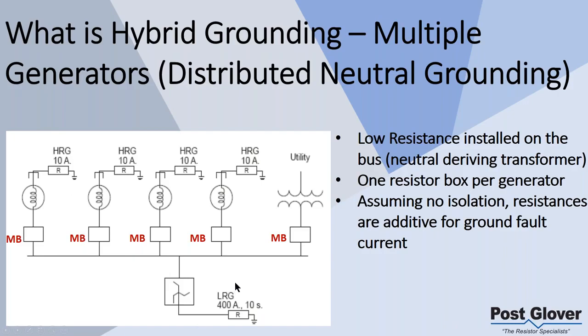But you essentially have the low resistance ground resistor hanging off of your bus right here, off of 3 wires. You're going to be deriving the neutral with what here is a zigzag transformer. So you have a neutral here. You have your resistance grounding off the low resistance ground right here. Per generator, you have a high resistance ground, typically a resistor-only package. And what happens here is you essentially trip off your main breaker if you have a fault inside your generator. If you do not, the ground fault current here is all additive.